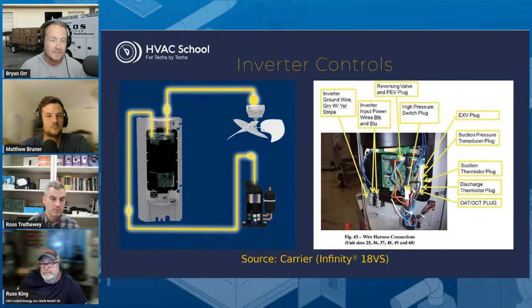So the way that these systems compensate for that, very similar to how ECM blower motors did when we were trying to get more airflow out of them, is that when you have situations where you're not getting as much, they just spin faster. And that's what we're doing. Once again, we're just spinning it faster. So now we can keep our capacity up, but you do that at a cost, meaning that it's going to draw more power the colder it gets outside still, because you're still fighting against this compression ratio problem.